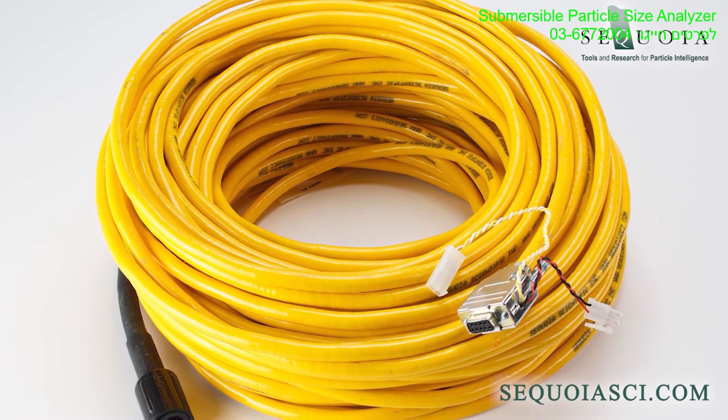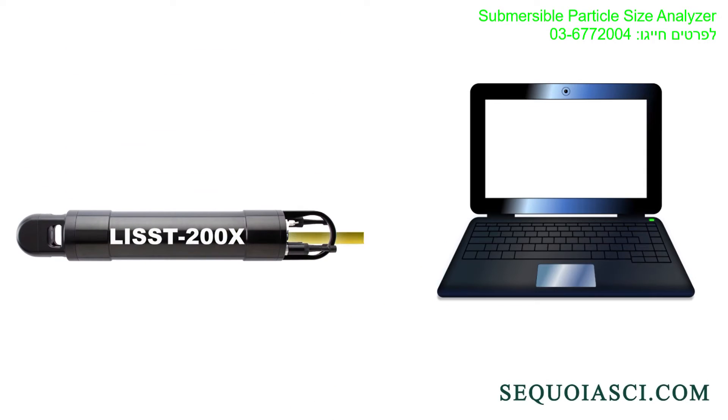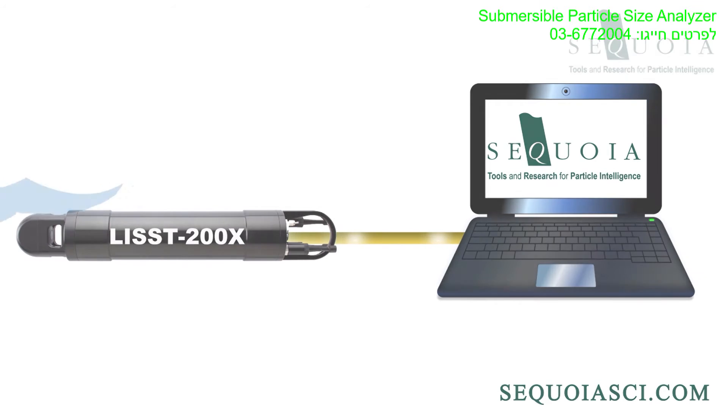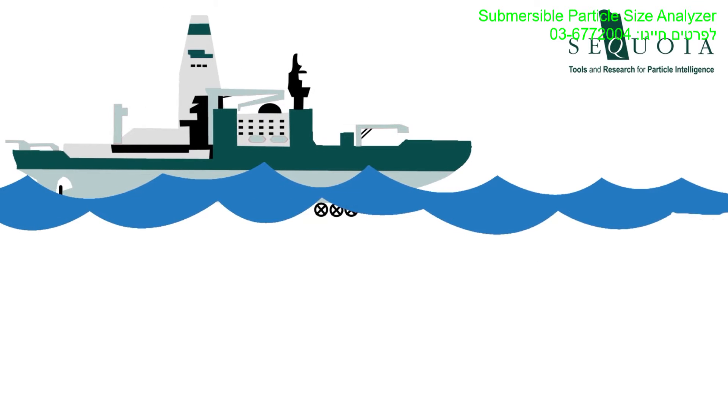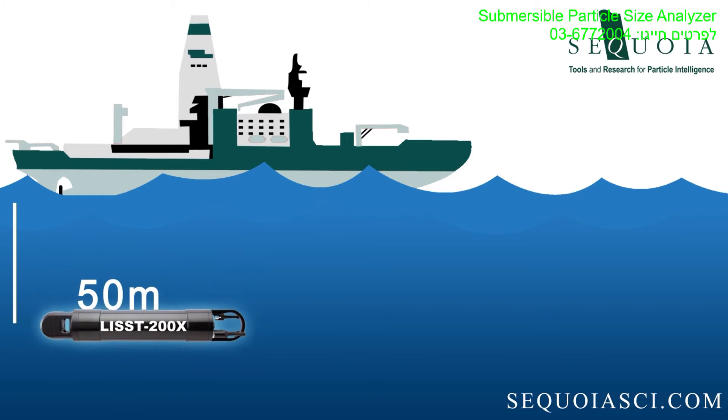Second, with Sequoia's LISST-200X data cable, you can connect the LISST-200X to your laptop and collect data in real-time on your PC. For this application, the cable length cannot be longer than 50 meters, even if the instrument itself is rated to 600 meters.